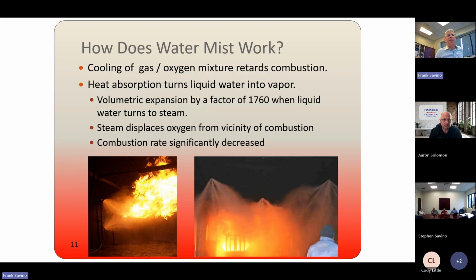So how does a water mist system work? It basically cools the gas-oxygen mixture, which retards combustion. If you look at the photo in the lower left, you'll see a very large flame, and then you'll see water mist being discharged into that flame. When it's discharged into the flames, the tiny water droplets will gasify to cool the flames. And so there's a flame inhibiting effect. Also, the heat absorption turns the liquid water into vapor, and in changing from liquid to vapor, it absorbs a tremendous amount of energy. The heat of vaporization of water is very, very high.